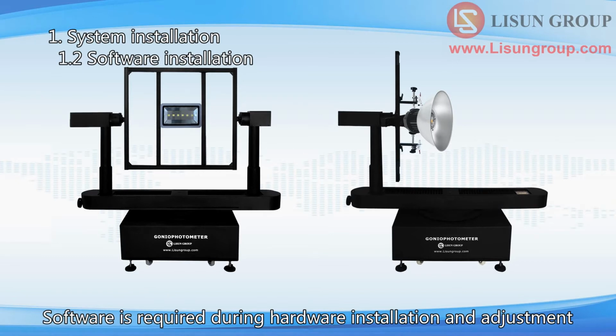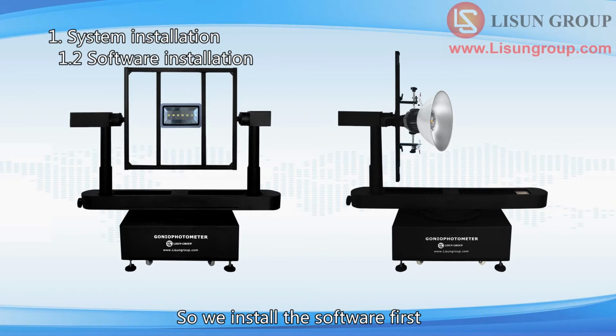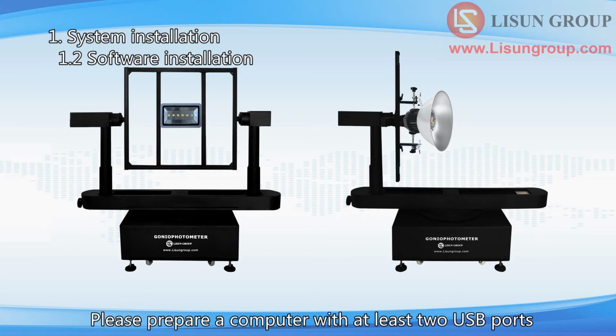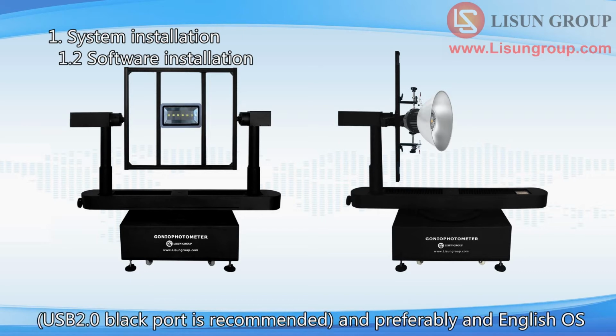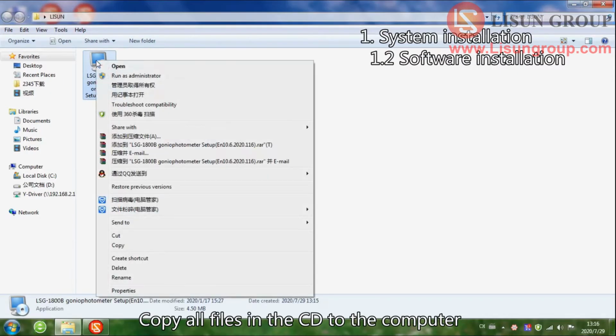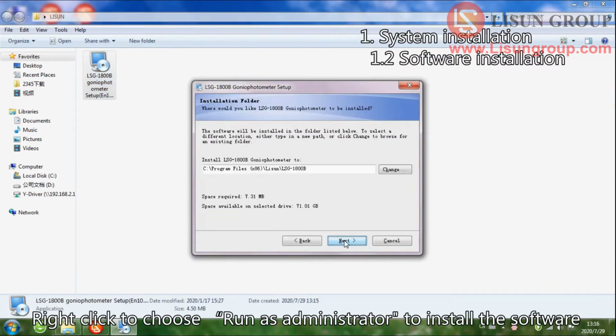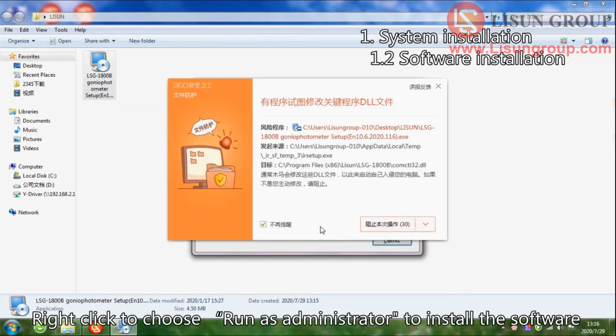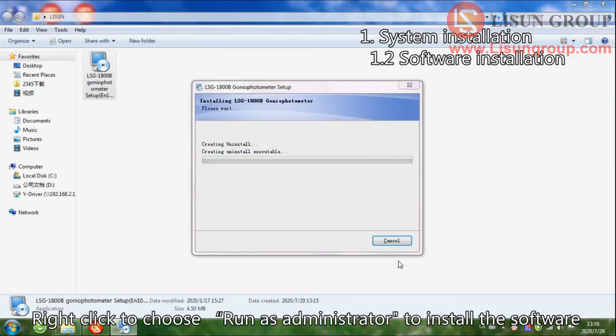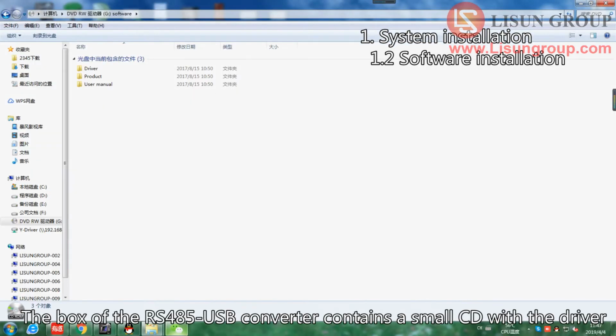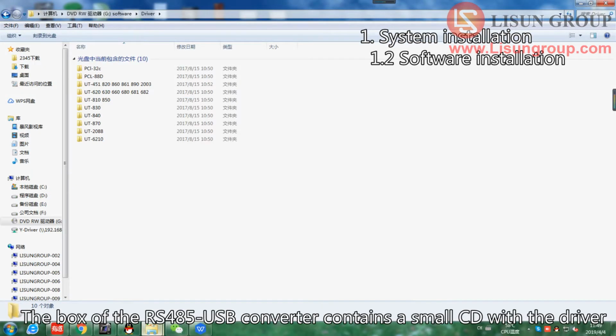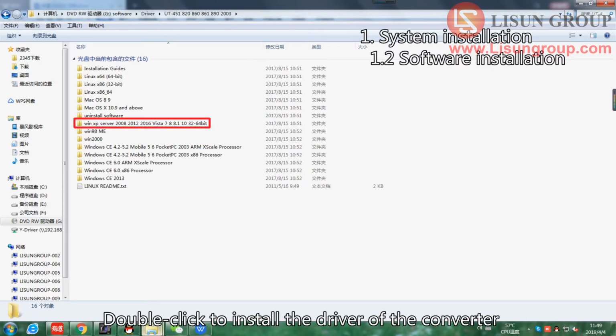Software is required during hardware installation and adjustment, so we install the software first. Please prepare a computer with at least 2 USB ports. A USB 2.0 black port is recommended, and preferably an English OS. Copy all files in the CD to the computer. Right-click to choose Run as administrator to install the software. The box of the RS485 USB converter contains a small CD with the driver. Double-click to install the driver of the converter.